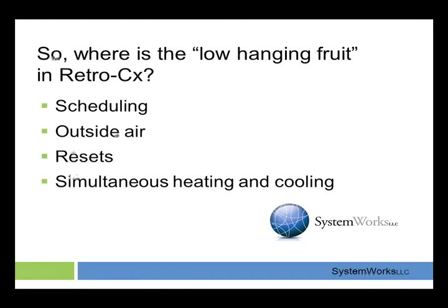So even if you're night cycling a unit, it shuts off at 3:30 in the winter time and comes on if it gets down to 60 degrees at night. When it comes on at night, the outside air damper should not open. Again, it's a real simple item, but it has to be programmed so that the unit only brings in fresh air or outside air during the occupied hours when students are going to be present.